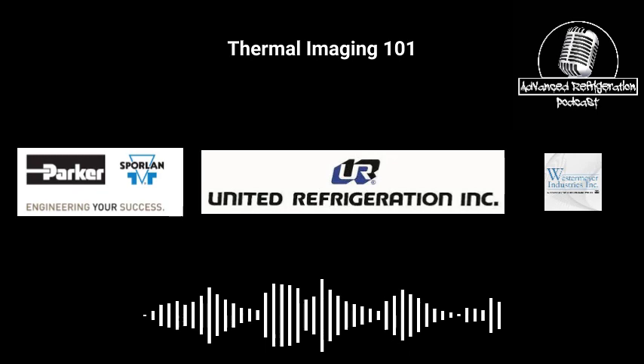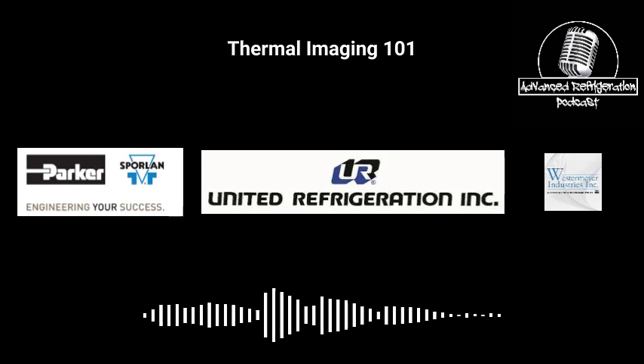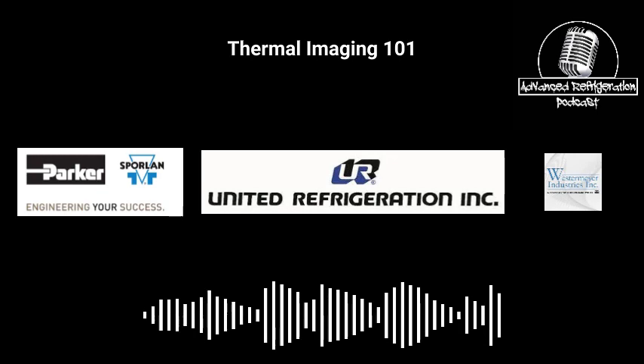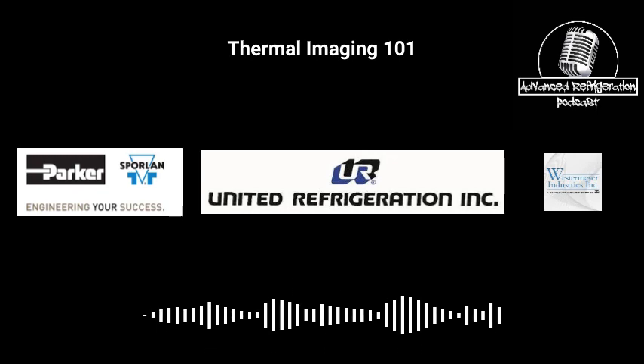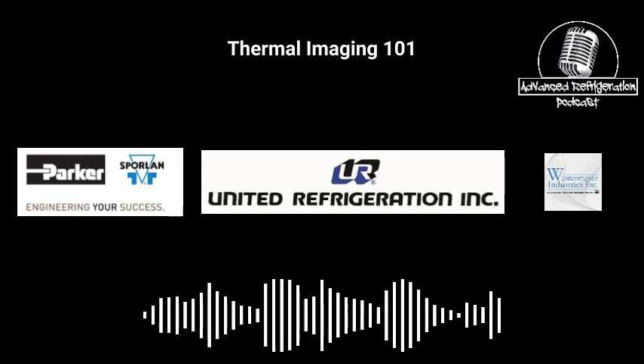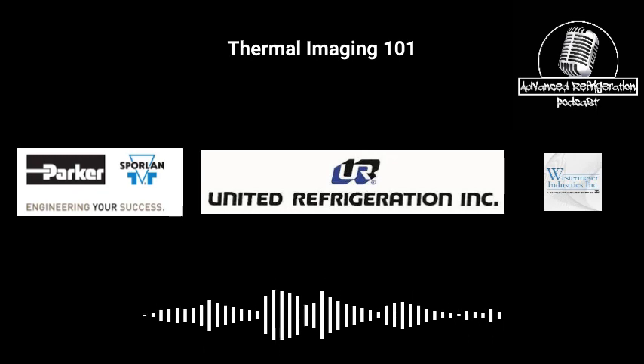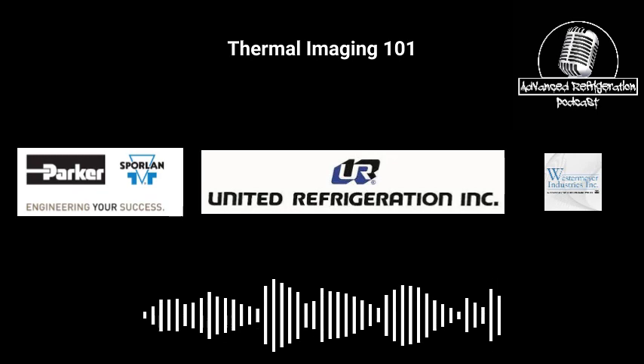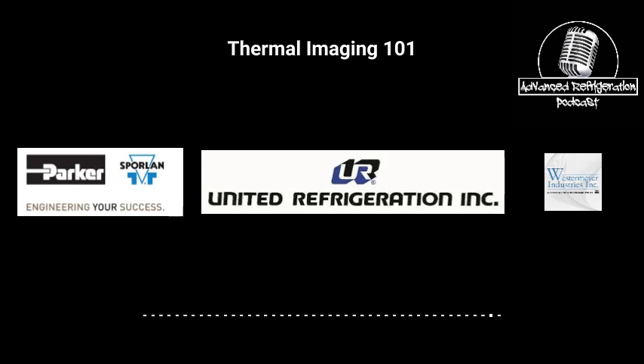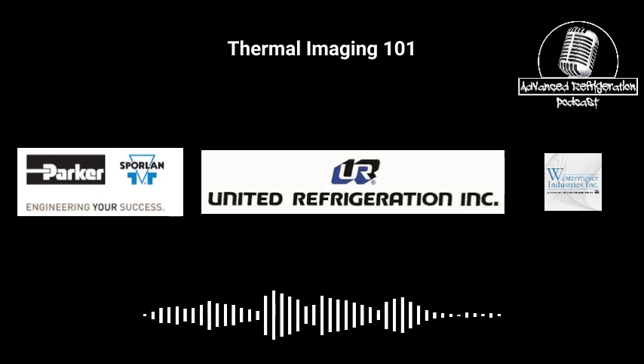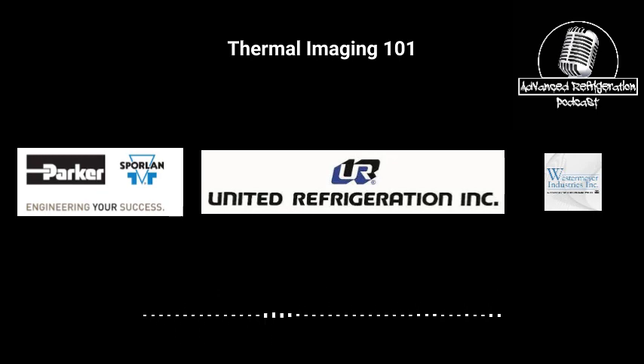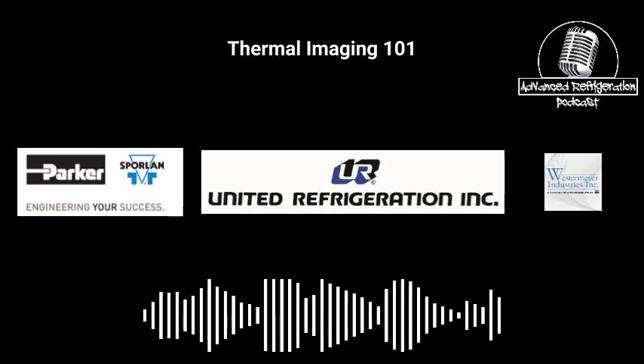It made our job so much easier, because we're able to go through these cases and see right away: okay, this case is going to fail the fast alert commissioning no matter what, because this section's warm, we're not getting airflow here, or we have air blowing into the case disturbing the airflow. We can see this vent is blowing into the case, causing the front product to run warm and the return to run warm. Then we're able to address that, adjust the diffuser a little bit, and now the case is back to blue, not high-temping in that section. That thermal imager makes that troubleshooting side of it a lot easier.